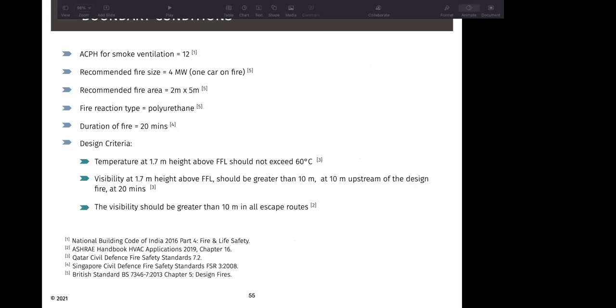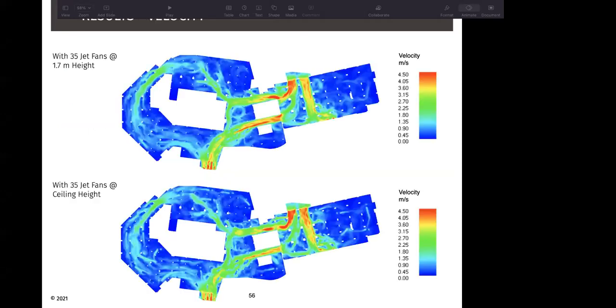In terms of boundary conditions, considering this is a fire analysis, we would have to maintain an ACPH of 12 for smoke ventilation. The recommended fire size for 1 car on fire is 4 megawatt, in an area of 2 meter by 5 meter. The fire reaction type is polyurethane for a duration of 20 minutes. The design criteria is that we need to maintain a temperature of less than 60 degrees and visibility of greater than 10 meters at 10 meters upstream of the design fire at 20 minutes. And the visibility should be greater than 10 meters in all escape routes.